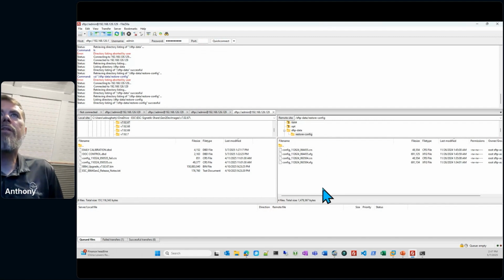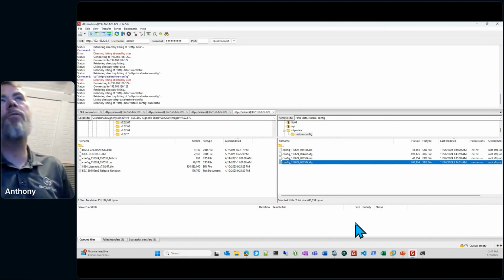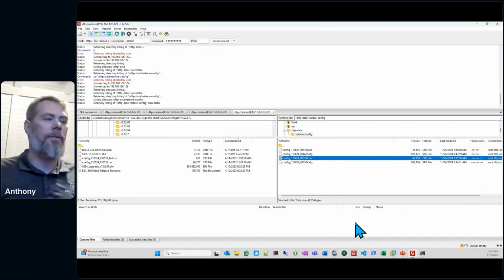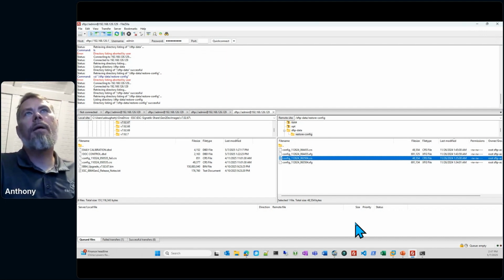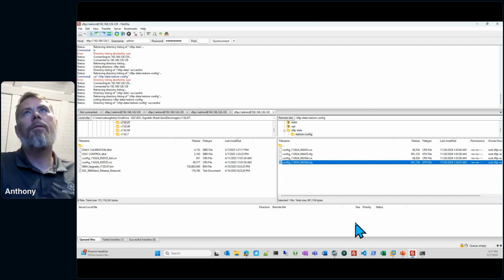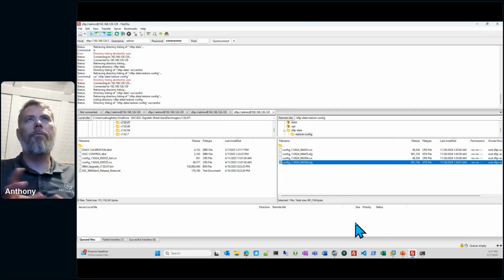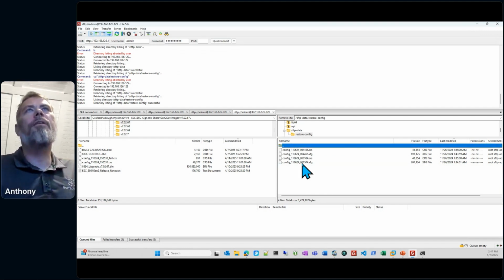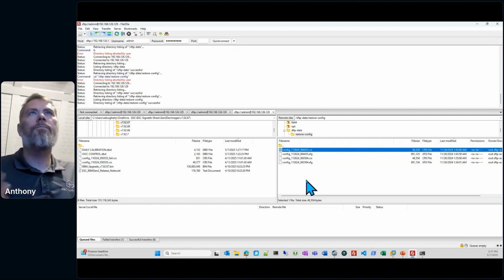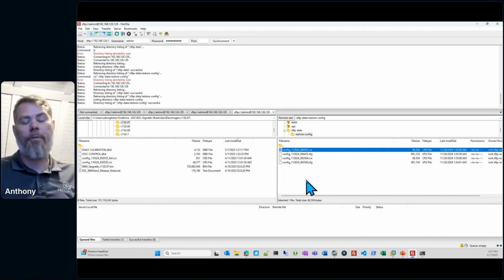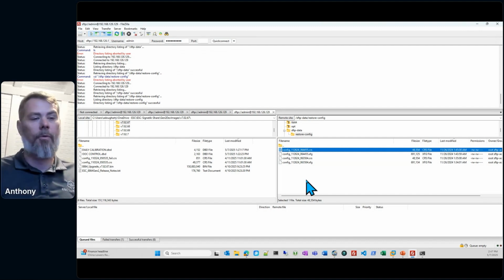All right, so if we go into here, what you'll see, there are two different files, and there'll be a server.cfg file here also if there was one present during the upload. This is the command response strings that were processed, and this is the actual configuration XML. And so if you really wanted to, you could go in here, rename that config XML, move it over, and do the process again. But if you needed to dig in and debug, if you do get errors, this is where you can go to pull a file or generate a system report, both before and after. I recommend generating a system report before and after doing this process. That way, if you ever do have trouble, you can give it to us and we can evaluate it, at least initially.